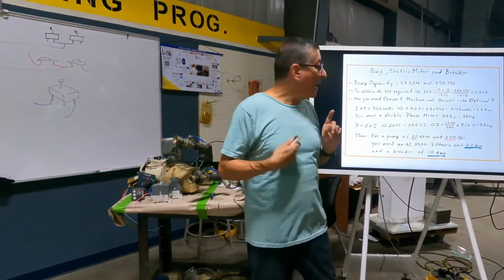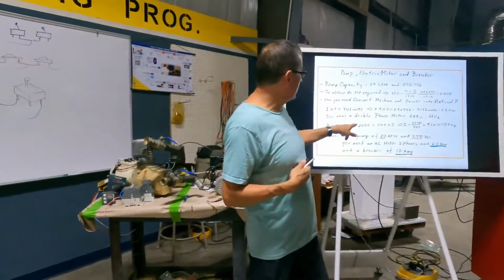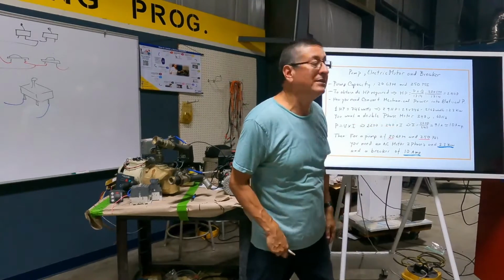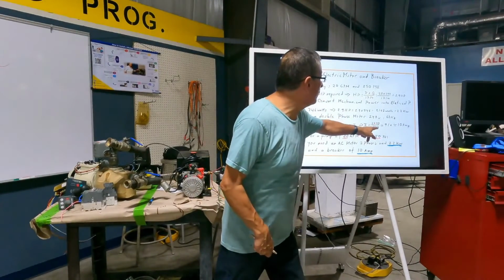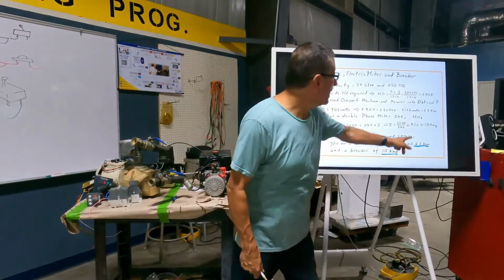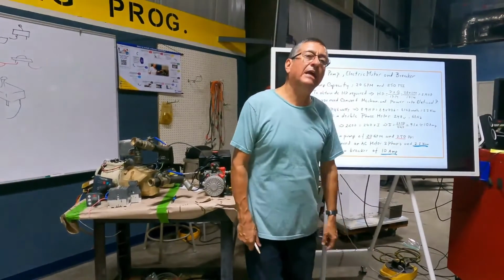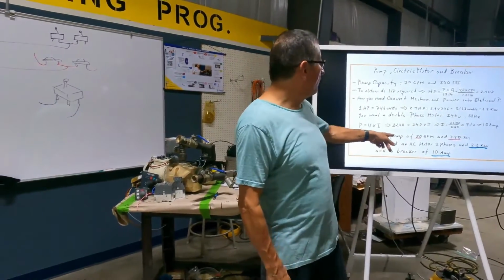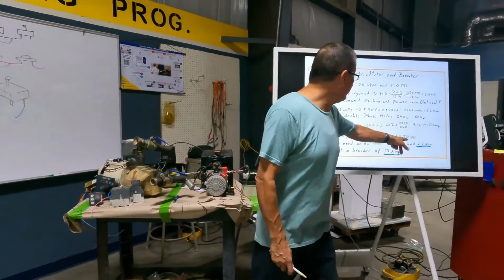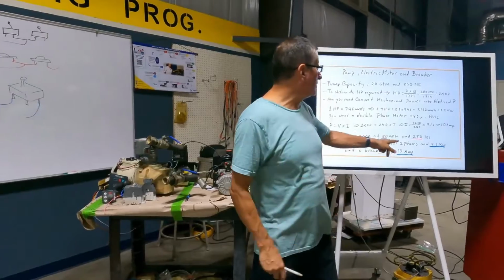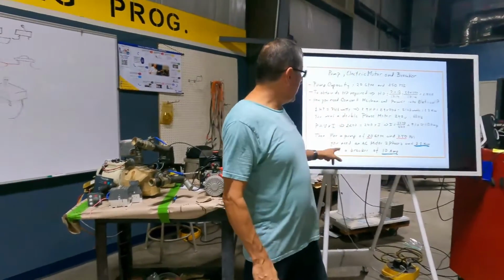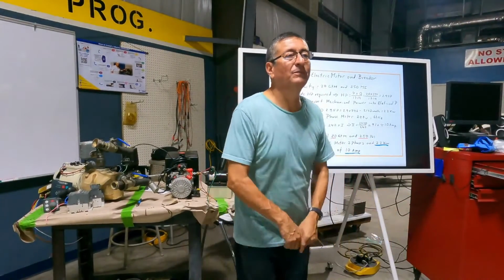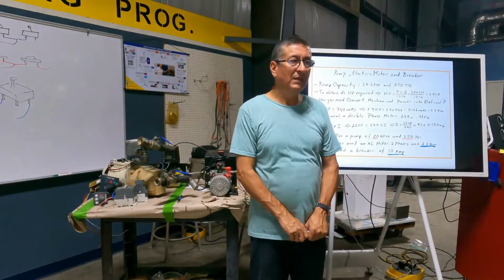Okay, pay attention. Power, 2.2 kilowatts, is equal to the voltage times intensity. The voltage is 240, I want to know the intensity. Okay, 2200 divided by 240 is 9.1 amps. I need 10 amps. This is the consumption, this is the breaker, 10 amps. Nice, no? Okay, for a pump of 20 gallons, 250 psi, I need a double phase motor, 2.2 kilowatts minimum, and I need a breaker with a capacity of 10 amps. Bingo, finito. Good? It's clear?